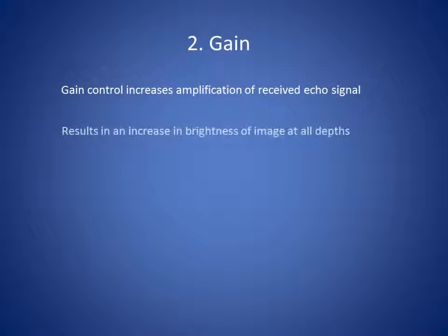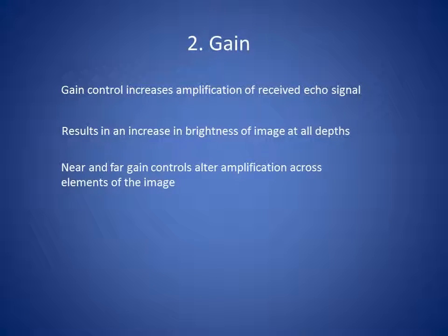The second control used frequently for vascular access is the gain control. The gain control increases or decreases the amplification of the received echo signal, resulting in an increase or decrease in brightness of the image at all depths. There is an overall gain control and near and far gain controls which alter the amplification across elements of the image only.